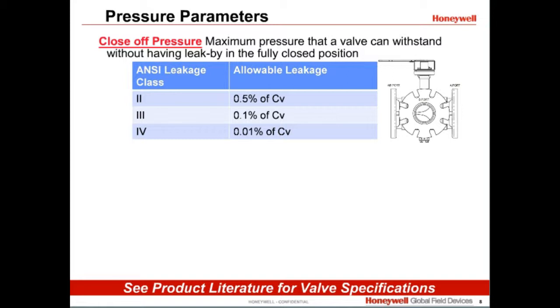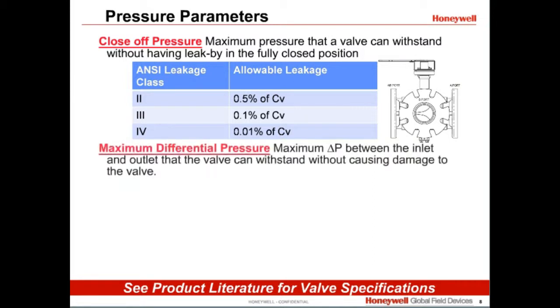For three-way valves, the valve must be able to close off against the pressure differential across the valve. The maximum differential pressure is the maximum pressure drop between the inlet and outlet of the valve that the valve can withstand without causing damage to the valve. This is the same as the close-off pressure for Honeywell ball valves.